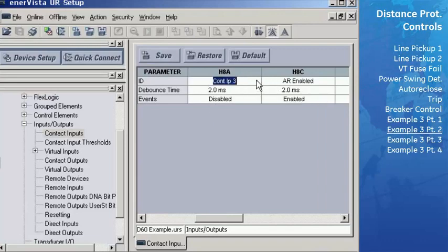Change contact H8A to circuit breaker open, indicating the breaker is open, and enable events. Change the name of contact M7C to breaker low pressure, indicating low pressure in the breaker, and enable events. Change the name of contact M8A to manual close, indicating a manual close command, and enable events. Then save these settings to the settings file and close this window.